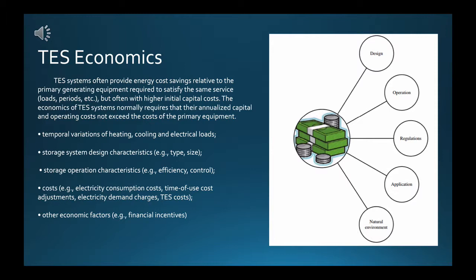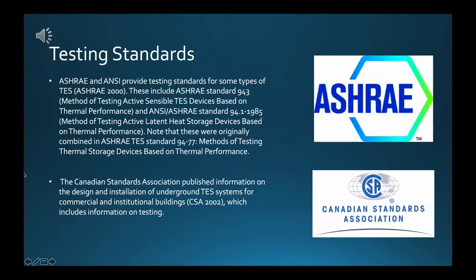TES systems can be applied cost-effectively in many residential, institutional, and commercial buildings, often exhibiting payback periods under 3 years. ASHRAE and ANSI provide testing standards for TES, including ASHRAE Standard 94.3 method of testing active sensible TES devices based on thermal performance, and ANSI/ASHRAE Standard 94.1 (1985) method of testing active latent heat storage devices based on thermal performance. The Canadian Standards Association also published information on the design and installation of underground TES systems for commercial and institutional buildings, which includes information on testing.